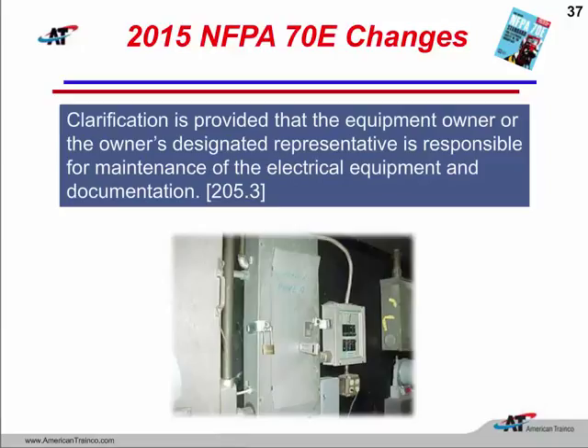Or possibly we might see a red label on the equipment. Maybe there is a 4160 volt breaker that was installed back in the 40s. It has never been turned on or off for the last 74 years, and it may be time to perform some maintenance on that. We're going to have to take that out of service. They don't want us to do anything energized with that. We would put a red label on that. So those labels are all independent of any labels that are required by 70E.